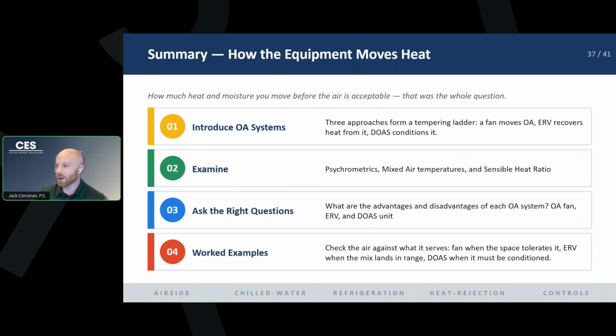You can see all of these air conditions on your psych chart, and you can tell from mixed air and your sensible heat ratio exactly where your entering and leaving air temperatures need to be in order to get a space temperature that's comfortable, right? For our human occupants, or if it's a warehouse, just your storage boxes. And if it's a clean room, your pharmaceutical drugs or compounding needs to be in that tight range. You can figure out exactly what that temperature of your supply air needs to be with the psychrometric chart.